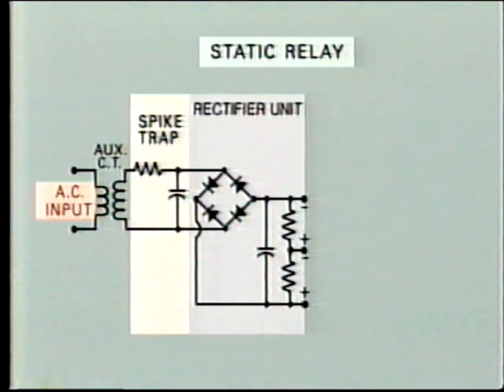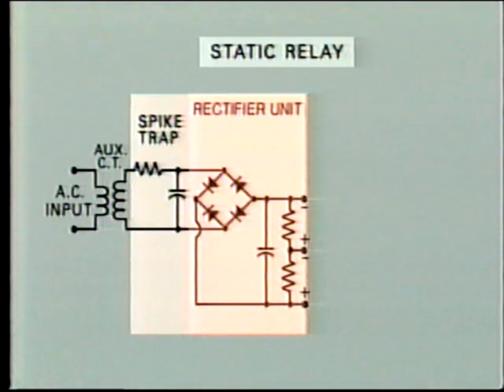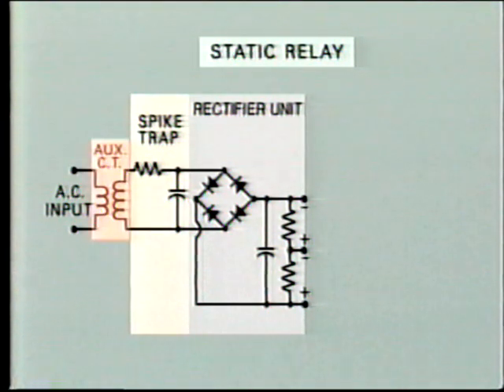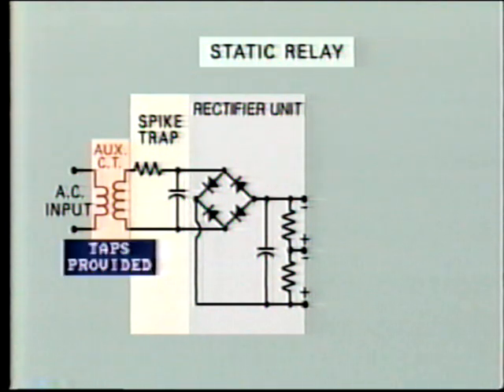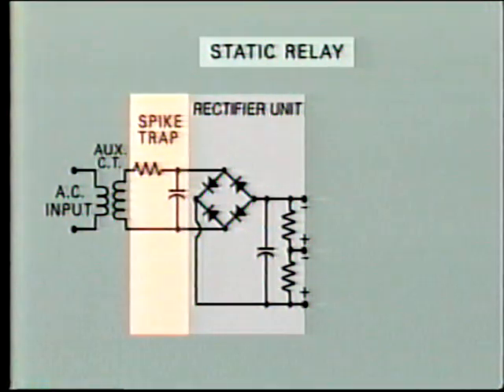This diagram shows us the incoming AC signal and its associated rectifier. The current from the CT is usually too high for the relay, and therefore an auxiliary CT is fitted into the relay. The ratio may be as high as 1,000 to 1, reducing, say, 5 amps to 5 milliamps. Taps are provided for adjusting the relay pickup and current range. An RC spike trap is normally located on the auxiliary transformer secondary. Full wave rectification is provided with a filter capacitor in the output.